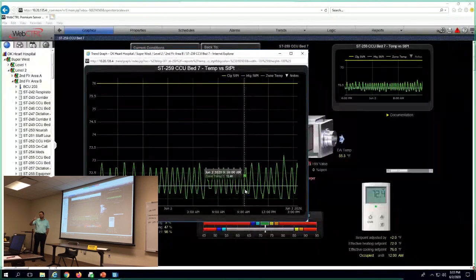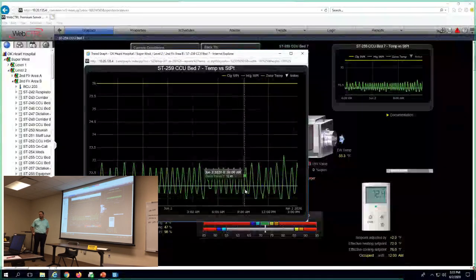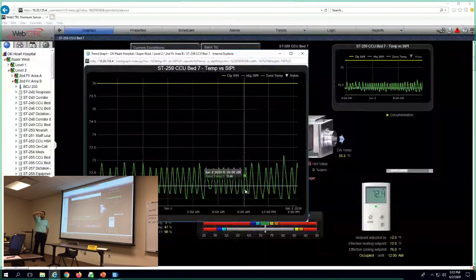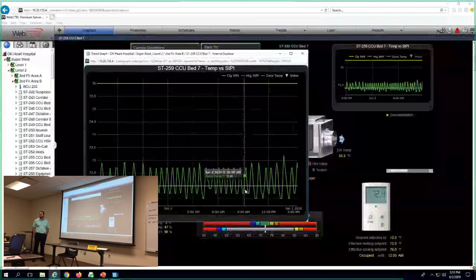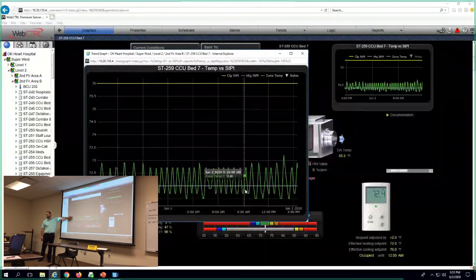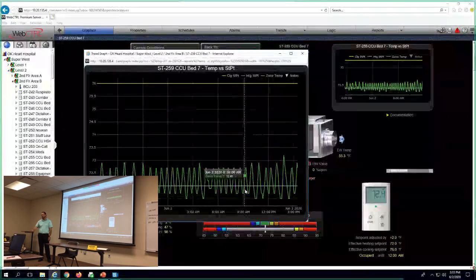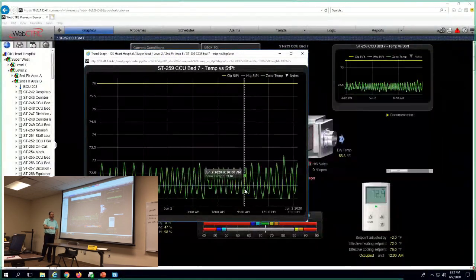Because you get the 2-degree deadband. Right. So if you run the set point up 4 degrees, it's going to heat up to 70. So Michael, why not have a 1-degree deadband? What are the implications there? There's obviously a trade-off here, right? You'll be constantly heating, cooling, heating, cooling, heating, cooling.